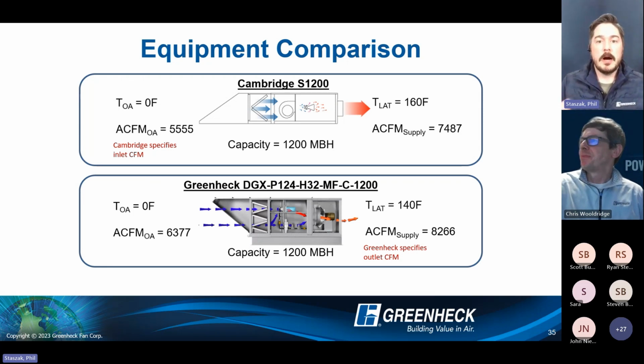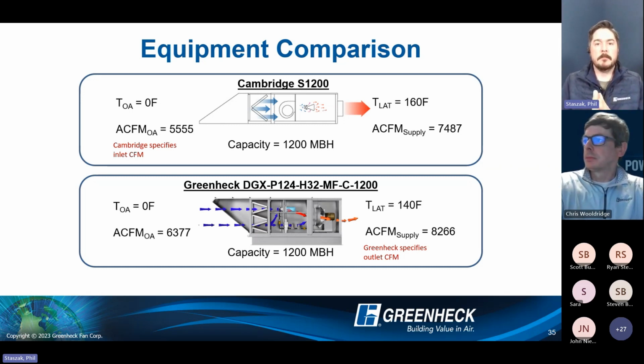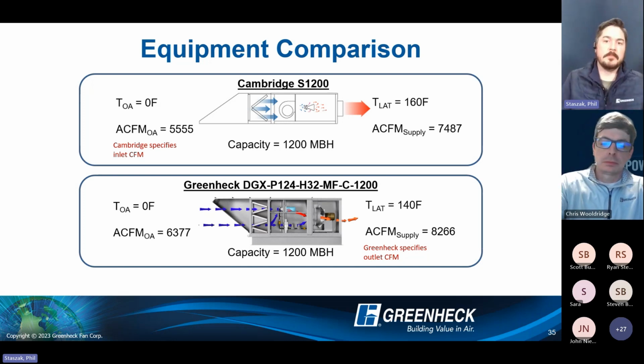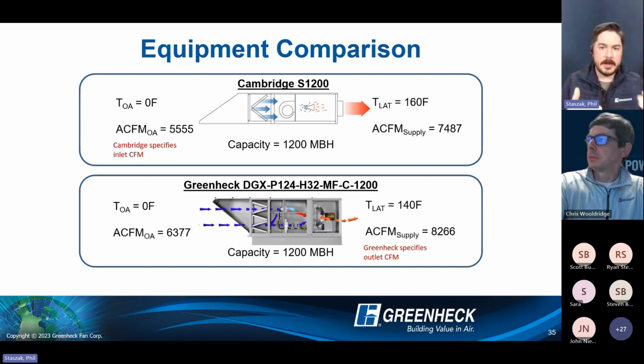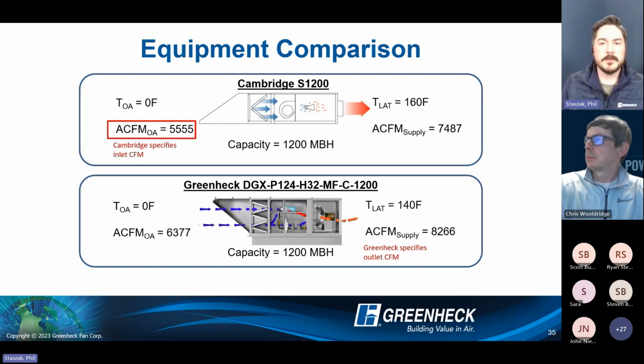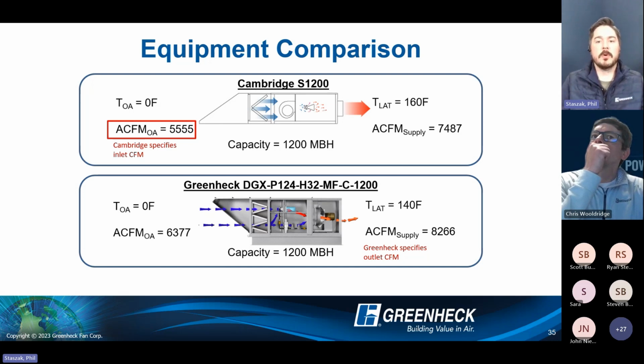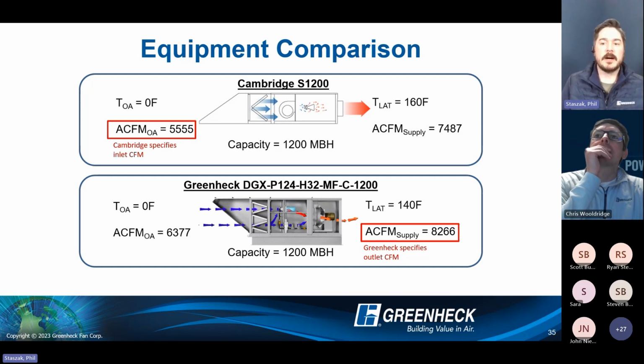Just wrapping up here. In case you've ever heard of Cambridge, just keep in mind what the Greenheck selection actually is. If you've ever heard of the Cambridge model, it is basically the same thing. Cambridge is a space heating direct gas fired unit, as is our Greenheck model. Now, just to clear up some confusion that often happens out there, Cambridge will specify inlet air because their blower is before the burner section. So it looks very confusing on a schedule for the 1-for-1 when you look at a direct gas fired Greenheck unit. We'll specify the 8,266 CFM being delivered into the building.